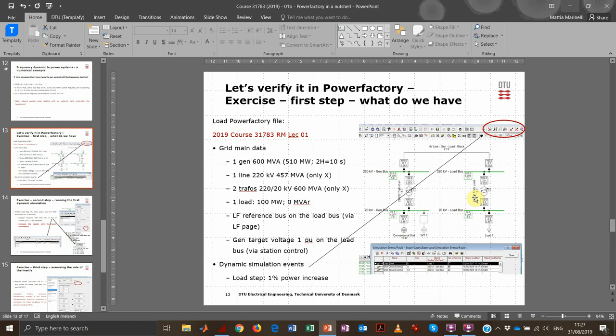Let's look at the first exercise in this course. We have our radial grid model. The grid is pretty straightforward. We have one generator, the size of which you can see here: it's a 600 MVA, 510 megawatt unit, and the inertia or time constant of the rotor — 2H — is equal to 10 seconds.